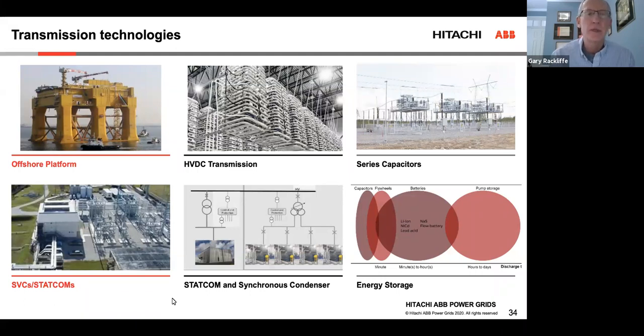Next, in the middle, the next picture is just an HVDC. This is showing the internal power electronics associated with the AC to DC conversion for HVDC lines. Series capacitors are not as relevant for offshore. These are more relevant for onshore wind, where you have long transmission lines and you can use the series capacitors to offset the inductance of long overhead transmission lines.